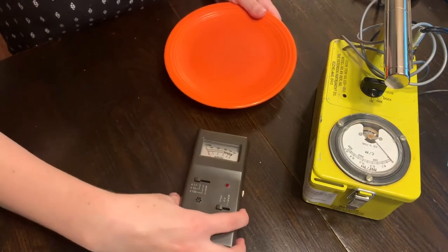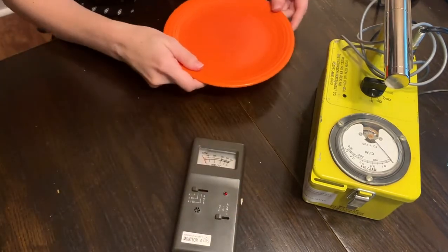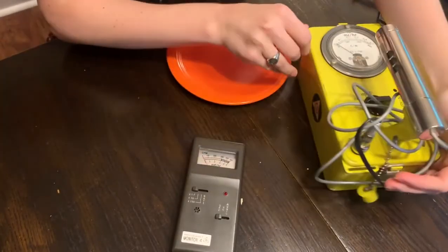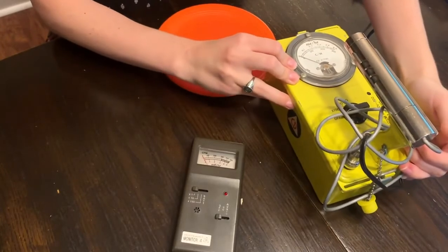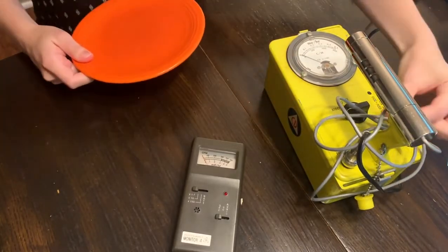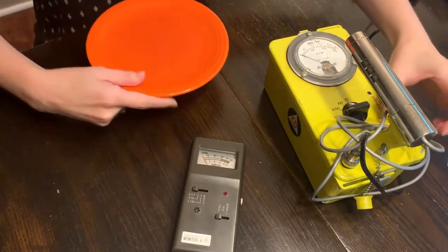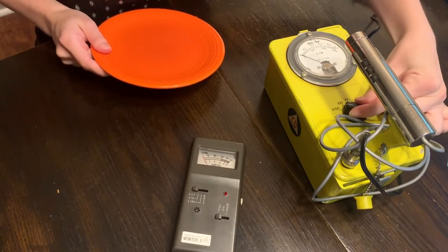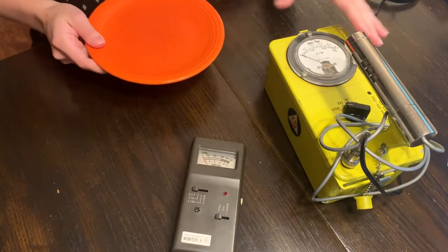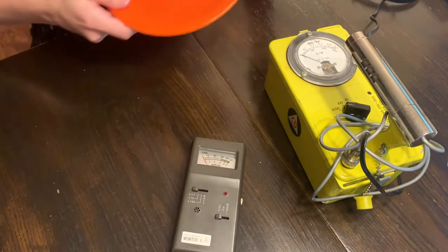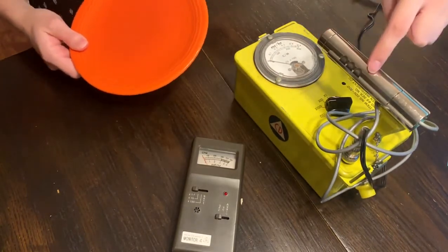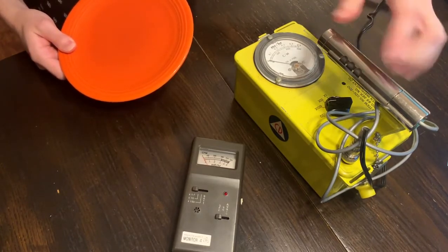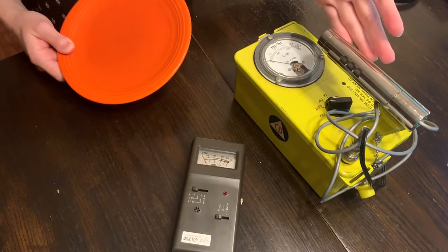So I'll go ahead, and I'm actually going to use both systems for this example so you guys can see how the yellow one works too. So the yellow one has a dial just like the Pocket, and you can turn it on to whatever setting you think is appropriate, and you can test it for whatever material you're using. And then what I'll do is I'll go ahead and put the material that I want to test by these sensor openings in the probe that does the radiation sensing.